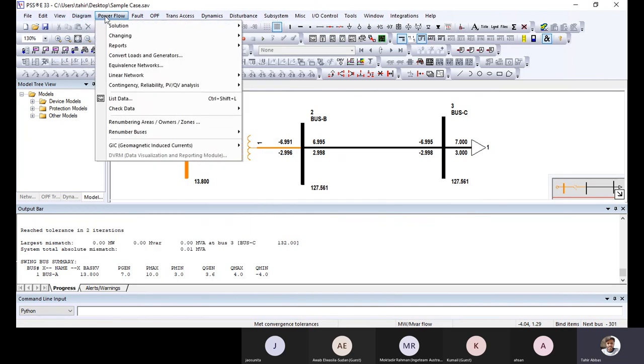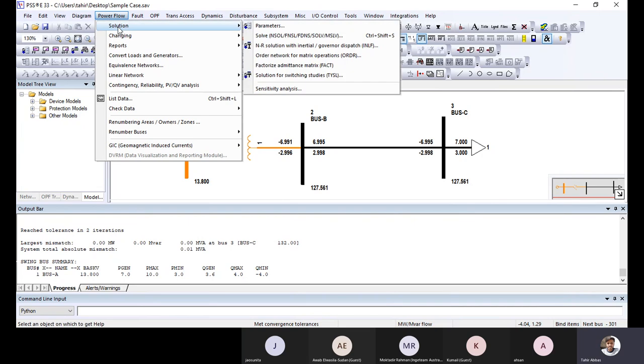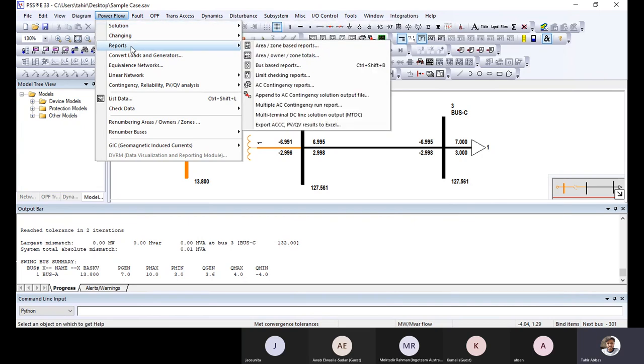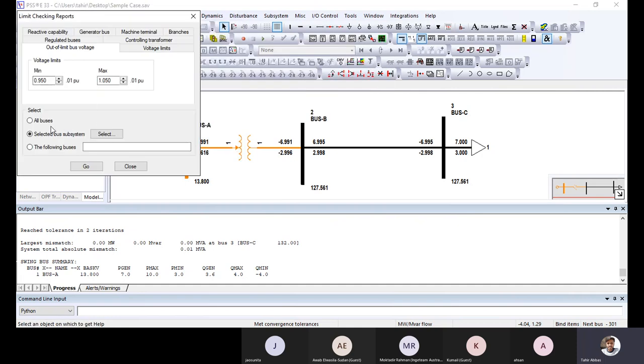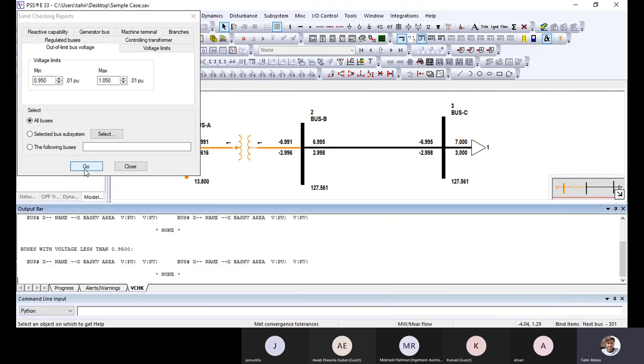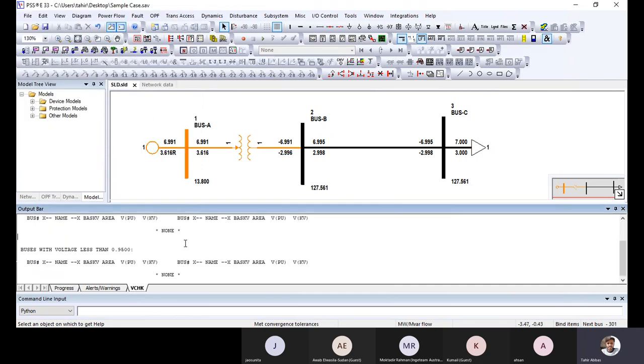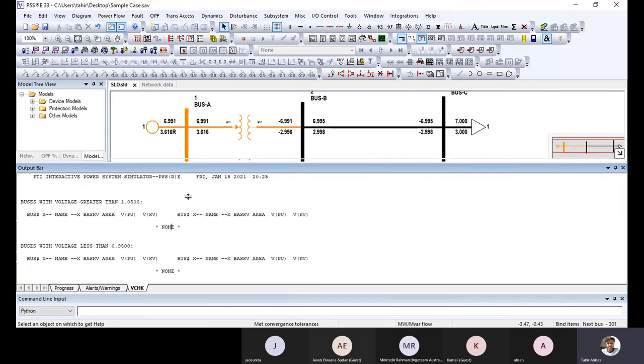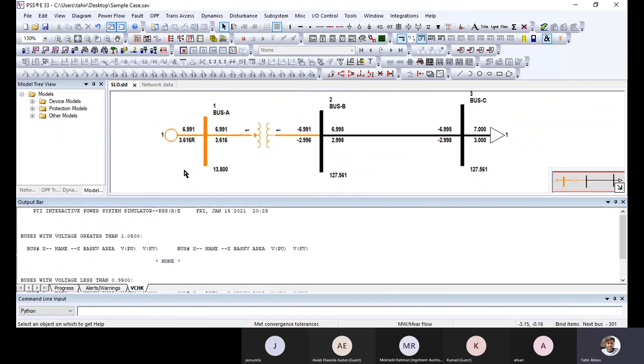And similarly in power flow, there is a solution tab. We can solve different analyses, and we can also generate different reports, like the limit checking report. I'm interested in the out of bus voltage limit, and I'm seeing all buses. I said okay. So the output is that there is no bus that is less than 0.95. In such a way we can perform the voltage check that we have seen in the presentation, the steady state performance criteria. Similarly, we will see all the analysis options, how we validate and how we perform the different analyses to check the criteria as per the study's requirement.